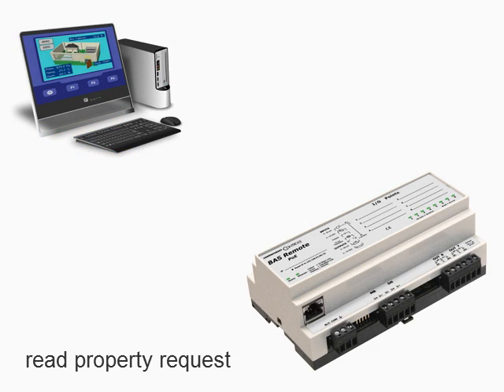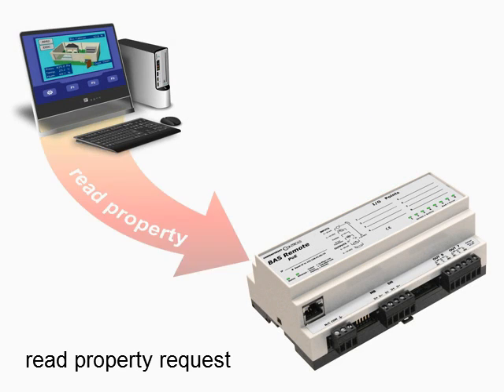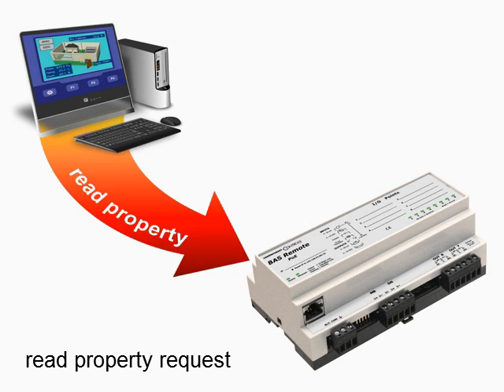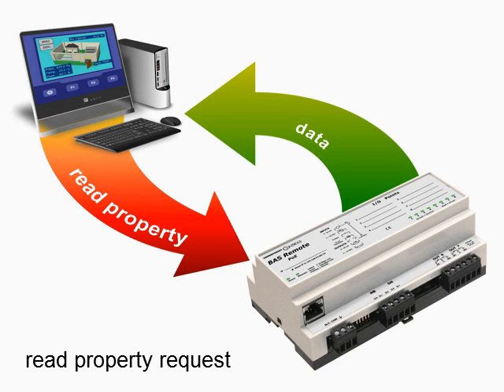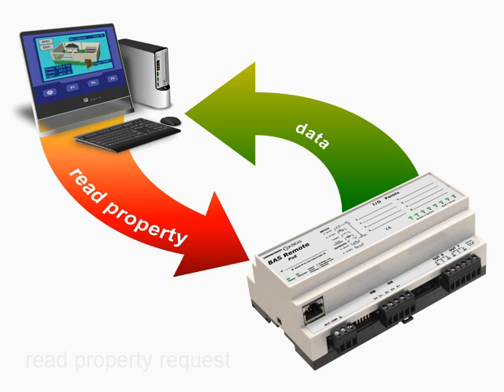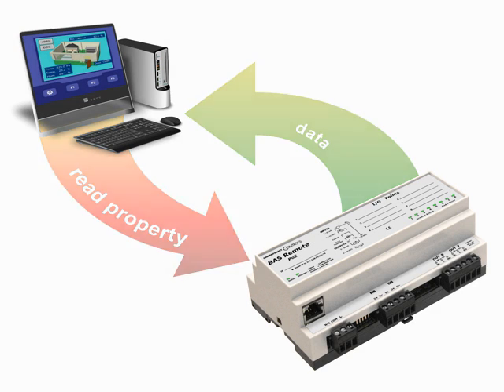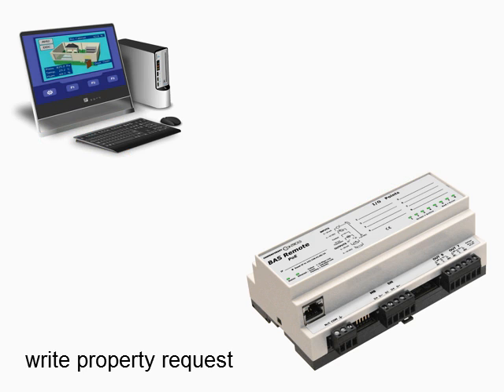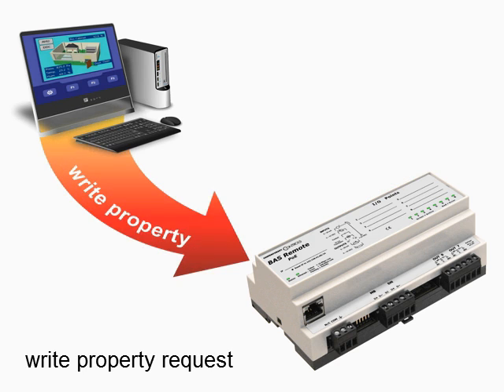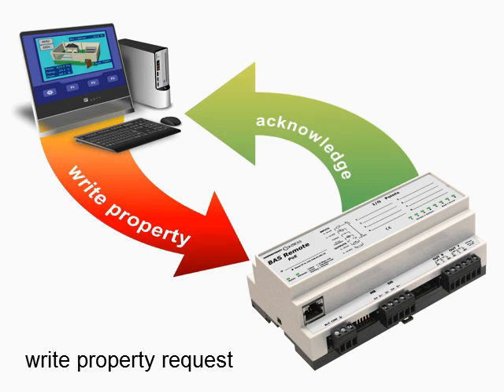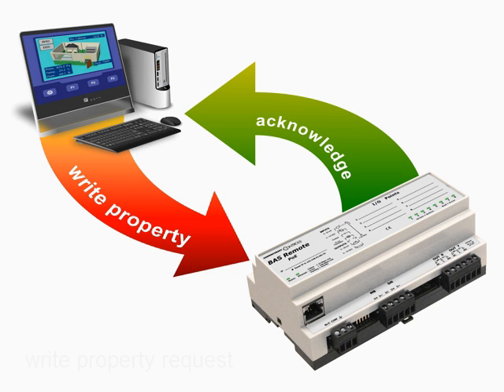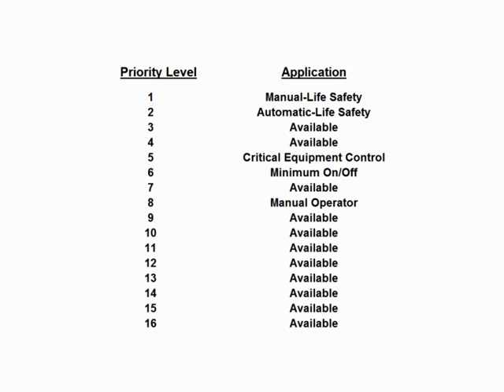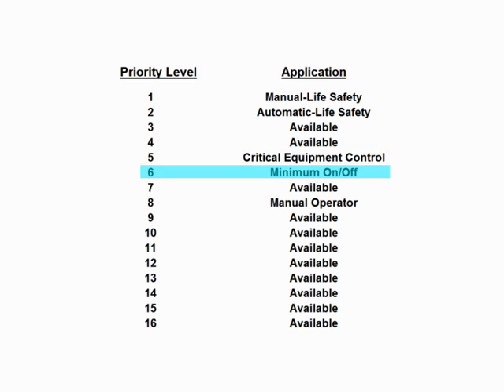In a read property request, the server will provide the value of the property indicated. In a write property request, a value is sent that changes the indicated property. Up to 16 levels of priority exist when writing values, thereby allowing for one client to take precedence over another.